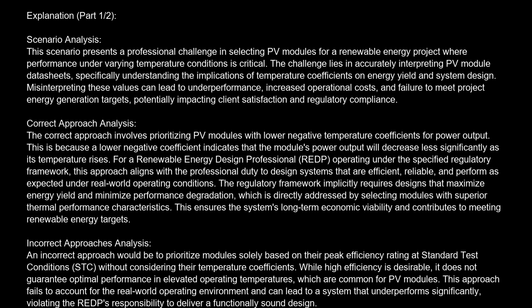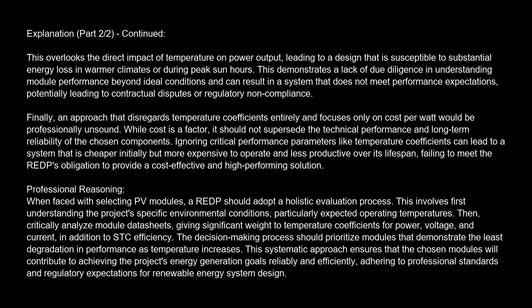Incorrect approaches analysis. An incorrect approach would be to prioritize modules solely based on their peak efficiency rating at standard test conditions, STC, without considering their temperature coefficients. While high efficiency is desirable, it does not guarantee optimal performance in elevated operating temperatures, which are common for PV modules. This approach fails to account for the real-world operating environment and can lead to a system that underperforms significantly, violating the REDP responsibility to deliver a functionally sound design. Another incorrect approach would be to select modules with higher negative temperature coefficients, assuming that any module with a good STC efficiency is acceptable. This overlooks the direct impact of temperature on power output, leading to a design that is susceptible to substantial energy loss in warmer climates or during peak sun hours.